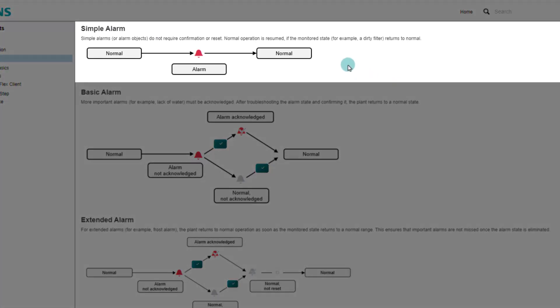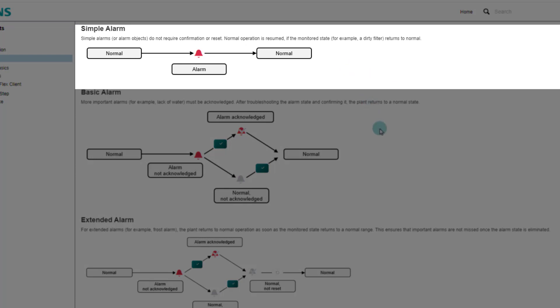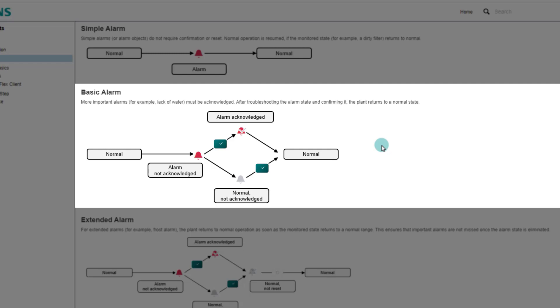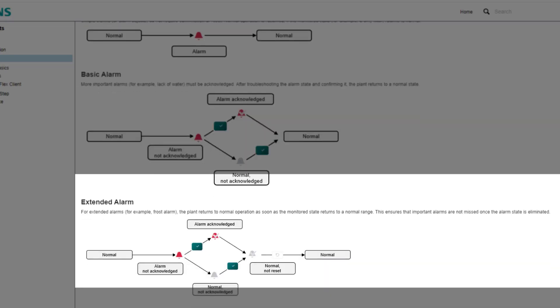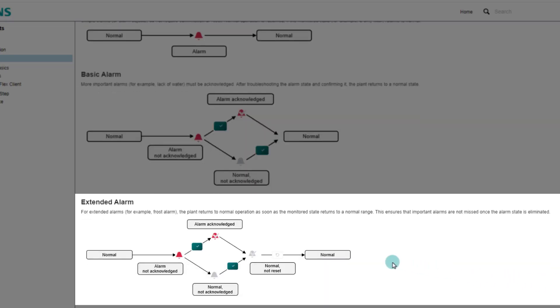Simple alarms return to normal once the fault has been cleared, without the need to acknowledge and reset. For basic alarms, an acknowledgement is necessary to reach the normal state. In the case of extended alarms, in addition to acknowledgement, it is also necessary to reset the alarm, and additional treatment that is used for important alarms.